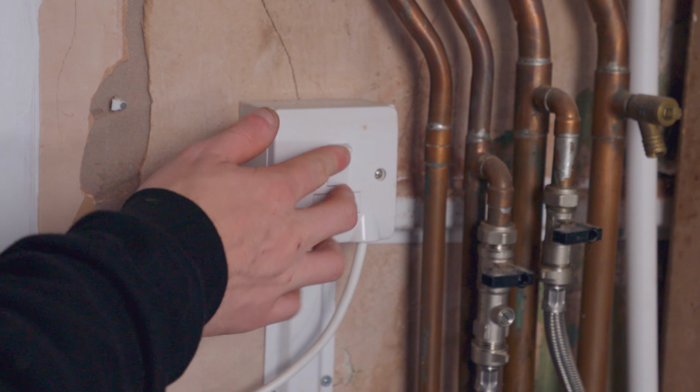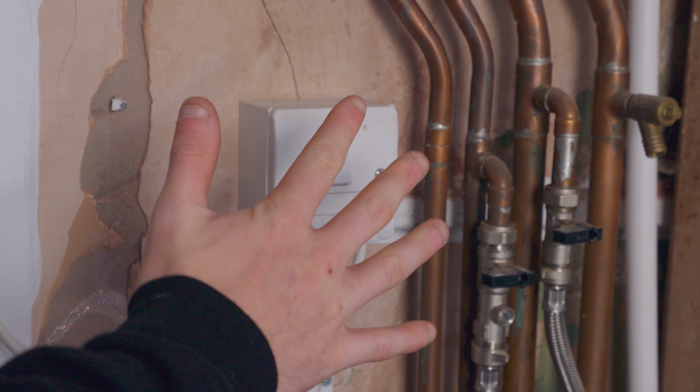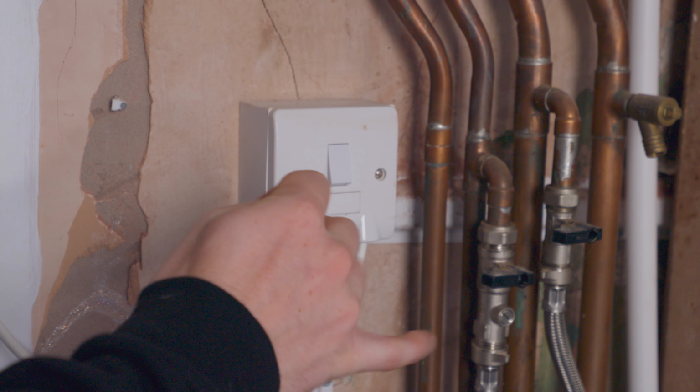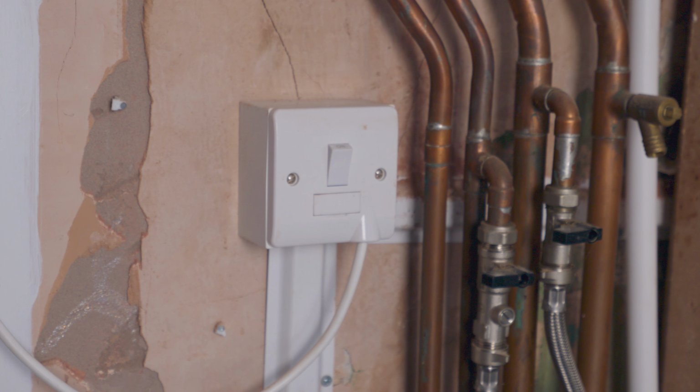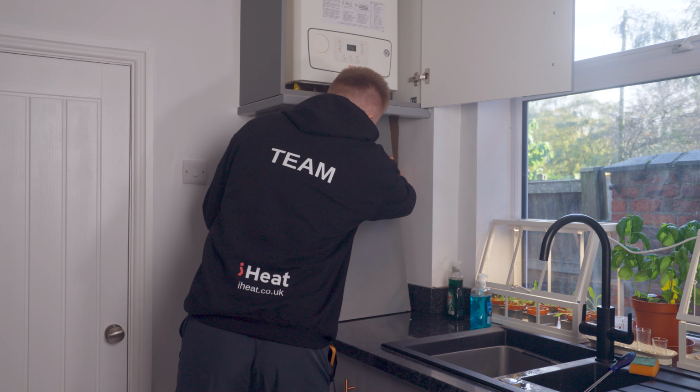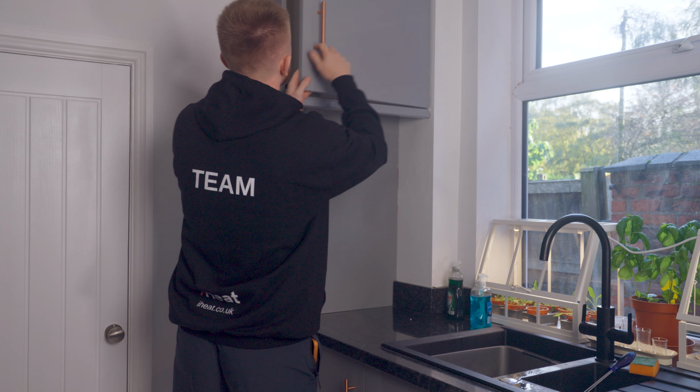Finally, a little trick: if your boiler doesn't have the reset button, head underneath or above to find the fuse spur. It's a quick switch, turn that on and off, and this will do the same thing. This isn't really recommended. It is better to use a reset button or reset set of buttons like on a Worcester boiler, but in a worst case scenario, it is an easy fix. I hope that helped, but if you do find yourself resetting your boiler quite a lot or getting a lot of error codes, it may be time for a new one.